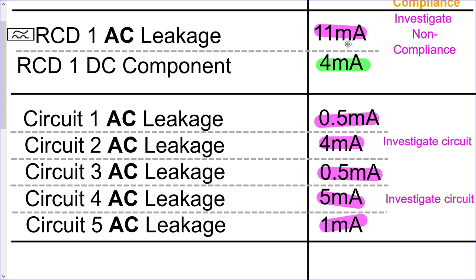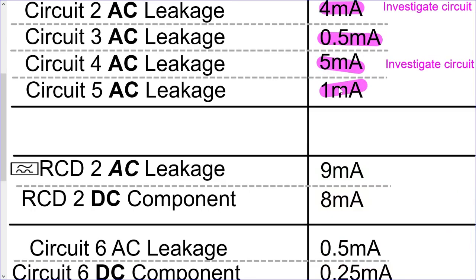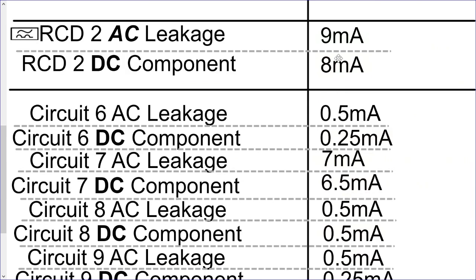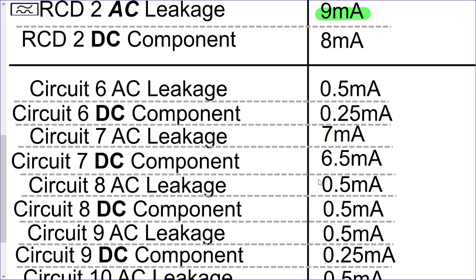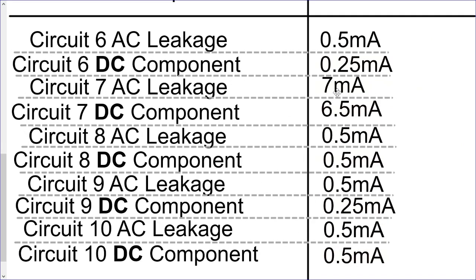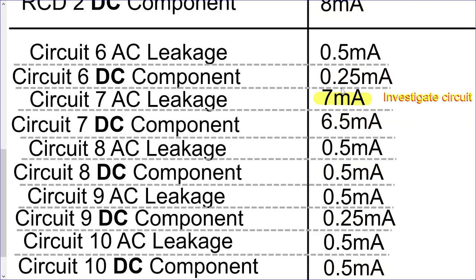overall leakage down. Okay. When we look at RCD2, you'll see there we've got 9 milliamps. Okay, so 9 milliamps on the AC leakage, type AC, that's perfectly fine. However, it is quite high. It's on that cusp of not complying. Okay, so when we're looking at the AC leakage for the rest of the circuits, you'll see there we have 7 milliamps on circuit number 7. So if we have 7 milliamps in circuit number 7, we're definitely going to investigate that circuit and find out what's going on. Again, possibly subdividing the installation more.